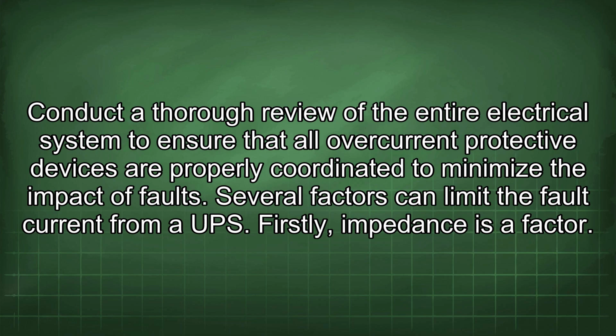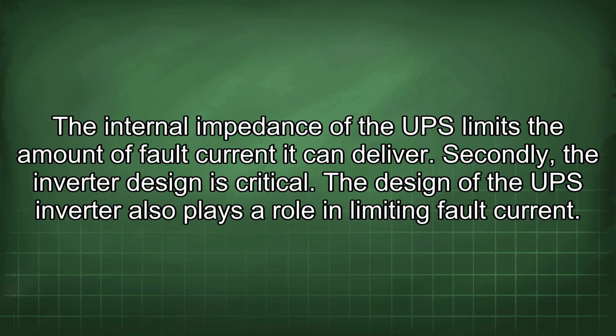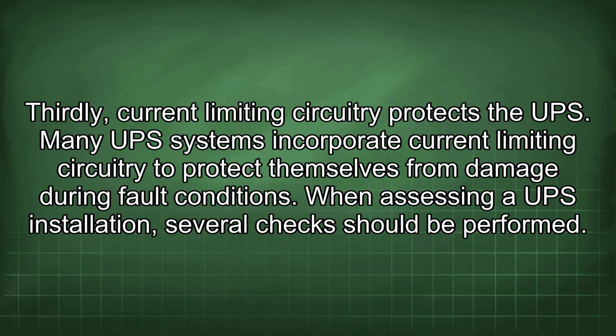Several factors can limit the fault current from a UPS. Firstly, impedance is a factor. The internal impedance of the UPS limits the amount of fault current it can deliver. Secondly, the inverter design is critical. The design of the UPS inverter also plays a role in limiting fault current. Thirdly, current limiting circuitry protects the UPS. Many UPS systems incorporate current limiting circuitry to protect themselves from damage during fault conditions.